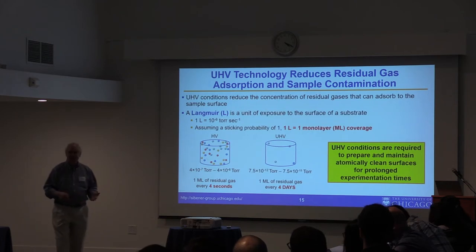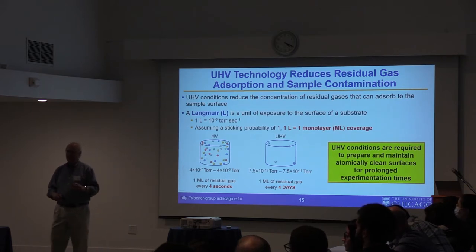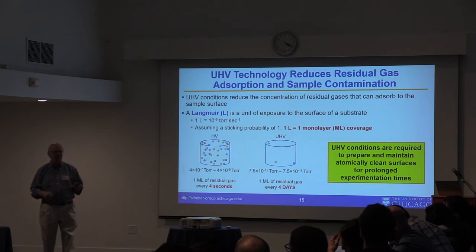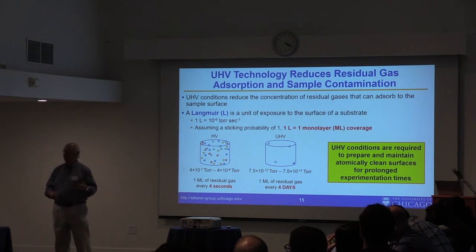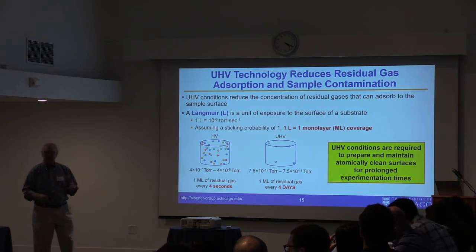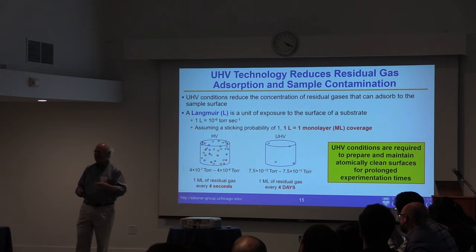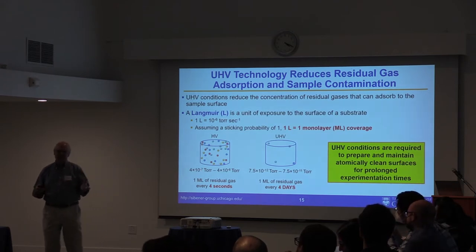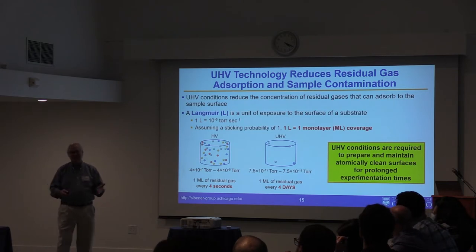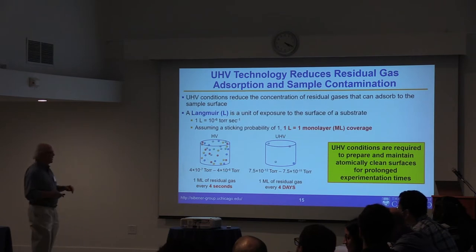I worked for Mark Cardillo as a post-doc — a very brilliant but entertaining person — and he had a saying: he never met a leak that he couldn't overcome with a big enough pump. The better solution: don't have a leak in the first place. He also wanted to write a paper claiming we were at 10⁻¹¹ torr, and when the pressure was about 1.5×10⁻¹¹, he said 'lower the temperature in the room' or 'touch it with an ice cube.' We got it down to 9×10⁻¹² — but you don't want to do it that way.